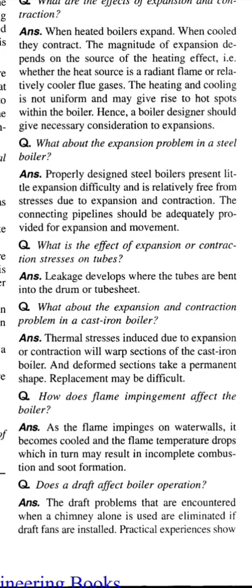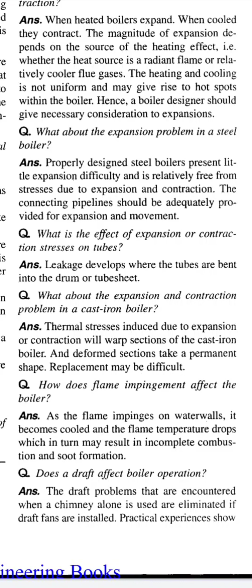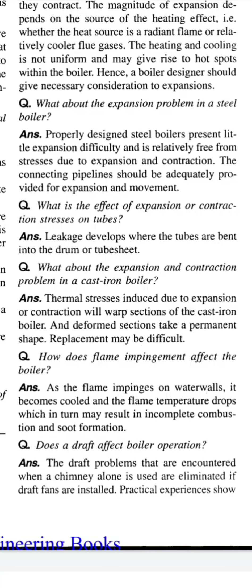Question: what about the expansion problem in a steel boiler? Answer: properly designed steel boilers present little expansion difficulty and are relatively free from stresses due to expansion and contraction. The connecting pipeline should be adequately provided for expansion and movement. Question: what is the effect of expansion or contraction stresses on tubes? Answer: leakage develops when the tubes are bent into the drum or tube sheet.